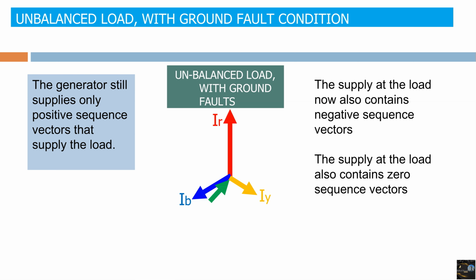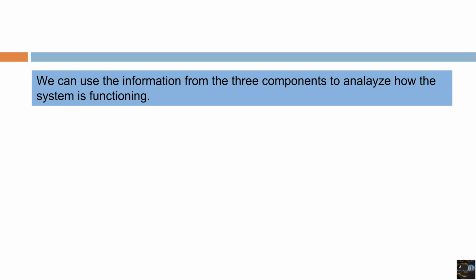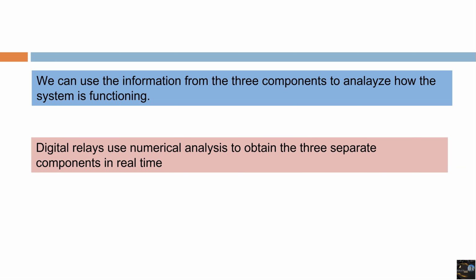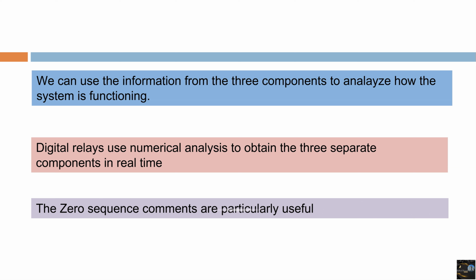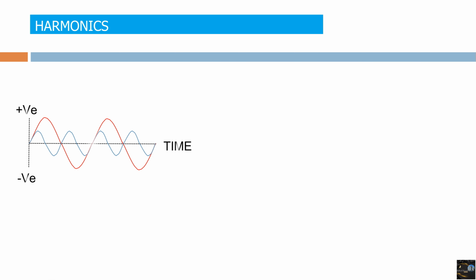Maybe you are thinking why we are bothering with all these things like balance, unbalance, and so on. Well, we can use the information from the three components to analyze how the system is functioning. Digital relays use numerical analysis to obtain the three separate components in real-time data, and the zero sequence components are particularly useful. And this analysis gives rise to the study of harmonic analysis. The typical waveform of harmonics you can see, time versus voltage, positive and negative value.